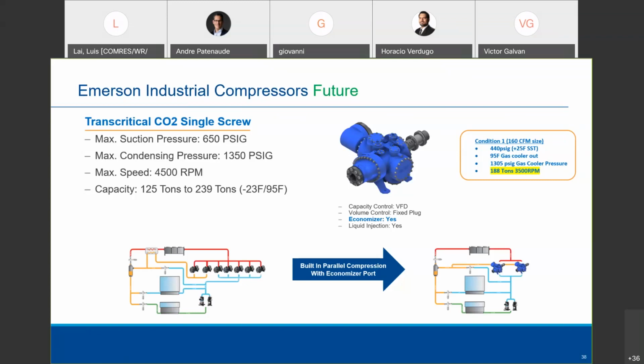Industrial or light industrial, and on my bi-weeklies, I've talked about industrial plants. There's one in Texas that has seven racks to do 3.6 megawatts of cooling. A lot of cooling, hundreds of compressors. You're taking a refrigeration supermarket mentality and trying to apply it to industrial. That's what's being done today, because some plants want to move away from ammonia and into another natural refrigerant. And they have to have these multi-parallel compressor racks.